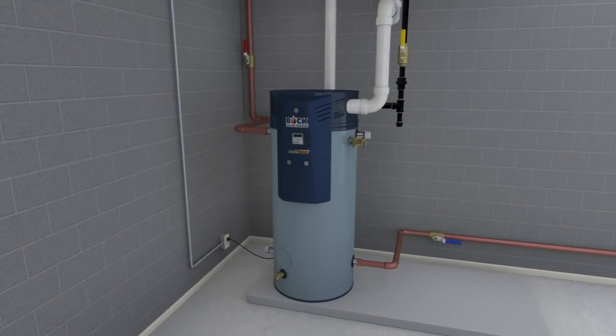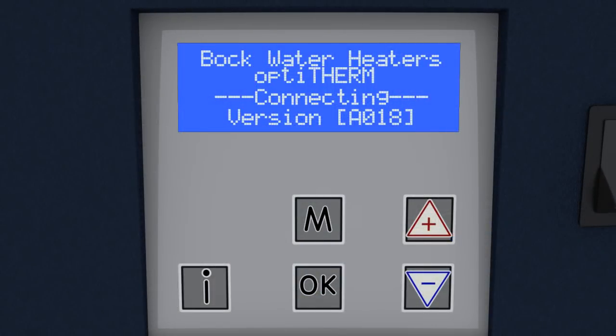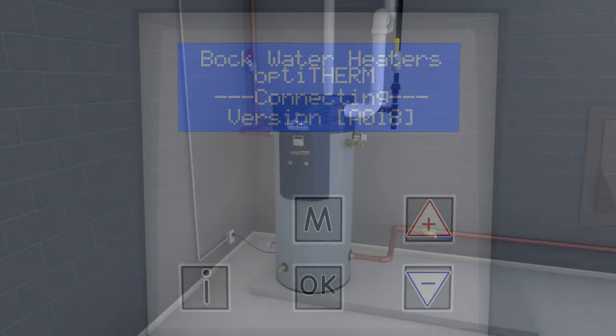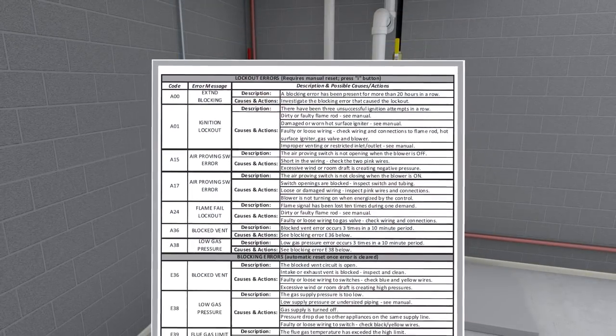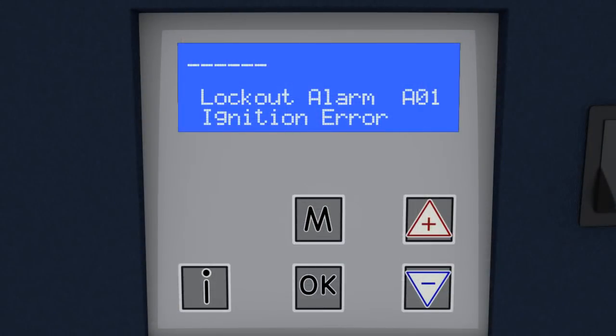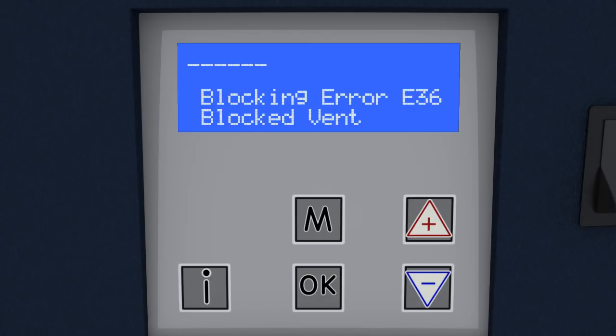A call for heat can be interrupted in many different ways. In most cases, the control display will help troubleshoot any problem by displaying a lockout or blocking error code. The error code list appears in the manual and on the unit. Lockout errors begin with an A and prevent unit operation until a technician performs a manual reset. Blocking errors begin with an E and also prevent unit operation, but will allow the unit to resume normal operation once the error is cleared. A blocking error can trigger a lockout error if enough blocking errors are recorded.